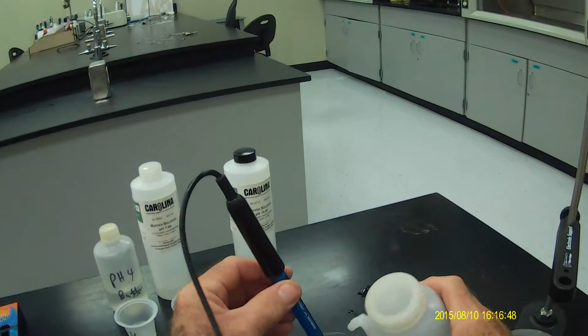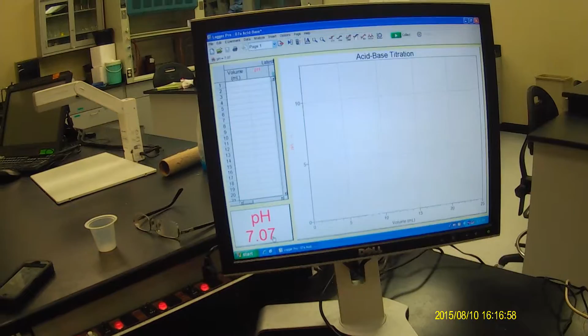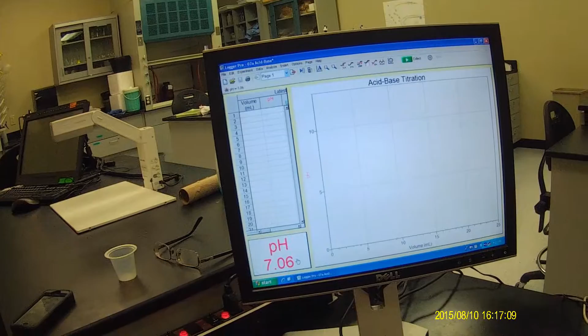Now to check, you can rinse this off. Go back and check the pH 7 buffer. Okay. Values plus or minus about a tenth, 0.07, is perfectly acceptable for these average pH meters. 7.06. So we're only 0.06, 0.07 of a pH unit, a little bit high. And you can see it's bouncing around a little bit.